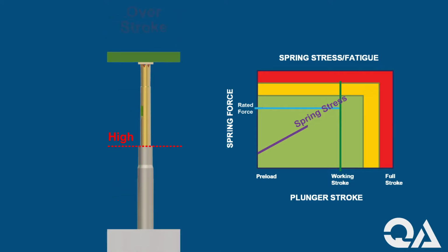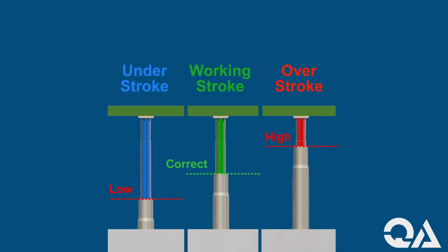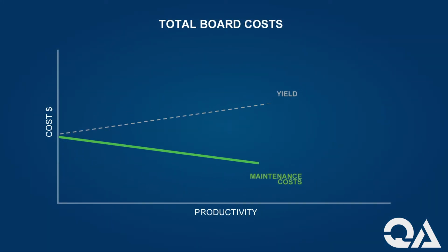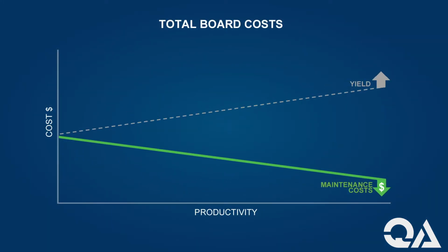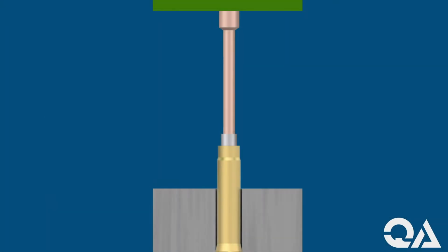Set too high, the plunger will be overstroked. This causes early spring fatigue, tip damage, or other premature probe failures. Setting probes at the proper working stroke will achieve the highest first pass yields, maximize probe life, and reduce overall maintenance costs. You can easily measure how much a probe will be actuated during test by using QA's indicator probes.